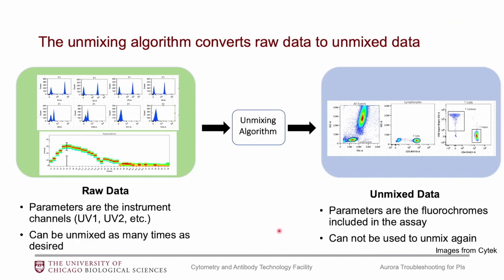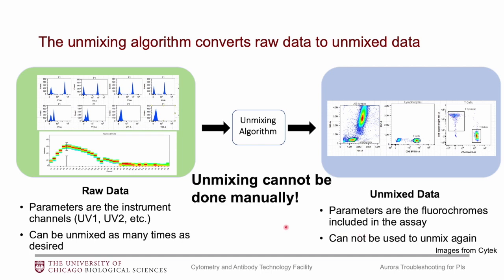When you're running the experiment, you're going to get raw data — FCS files that can be opened in FlowJo or FCS Express. If you open them, you'll see that the parameters are just the 64 detectors on the instrument. This data then goes through the unmixing algorithm, and you'll get a second FCS file containing the unmixed data, where the parameters are the fluorochromes included in the assay. Raw data can be unmixed as many times as you want, whereas unmixed data cannot be used to unmix again — so keep both FCS files. Also note that unmixing cannot be done manually; it has to go through the algorithm.